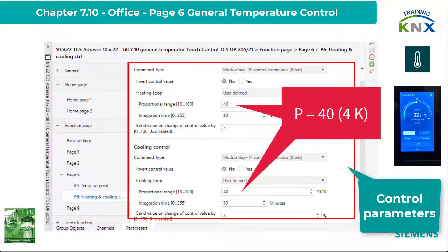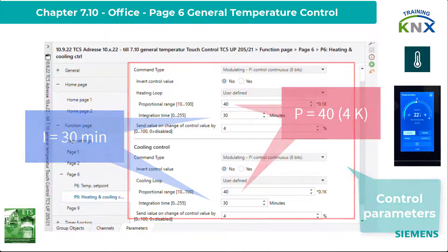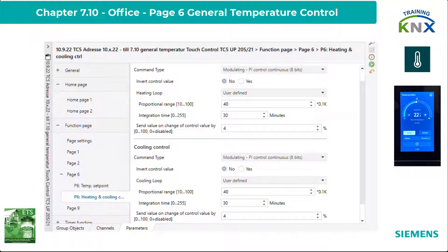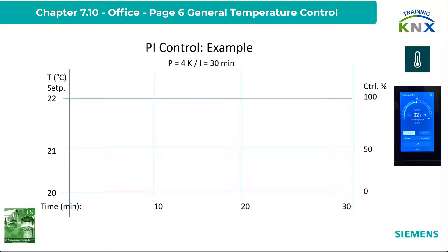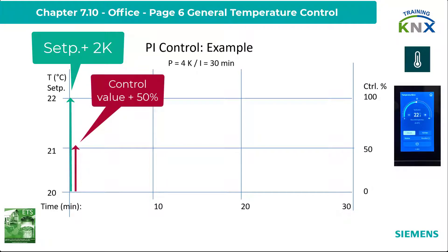For the command type, the control value remains direct — it could also be inverted if required depending on the actuator. The PI control parameters can be set separately for heating and cooling. There are four preset pairs of coefficients for certain types of heating, but experience shows that the values I enter here are more suitable even for underfloor heating. If you want to know exactly what these two parameters do, you can learn about them in the KNX Advanced Course or the KNX HVAC Specialist Course — both certified KNX courses with exam. So I set the P value to 40, which corresponds to 4 Kelvin, and the I value to 30 minutes.